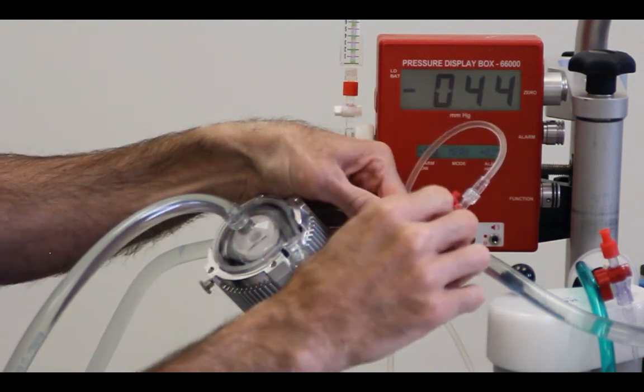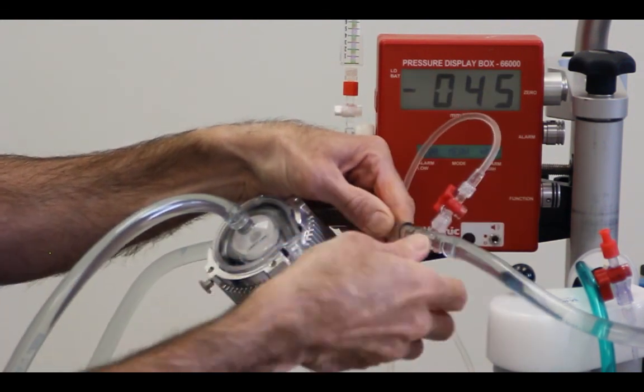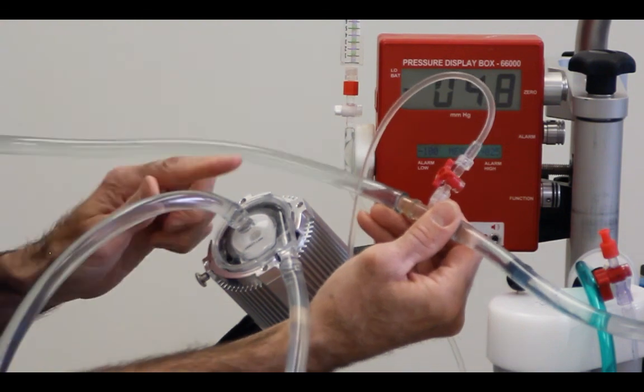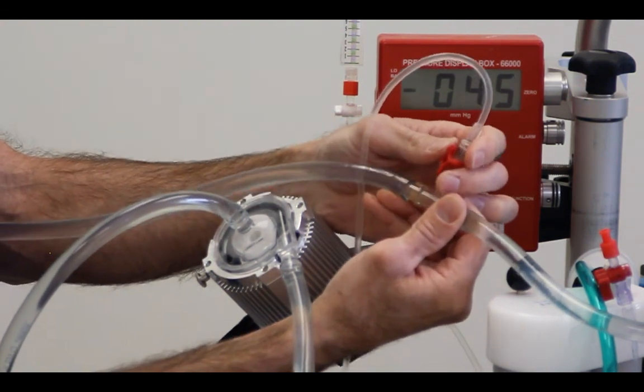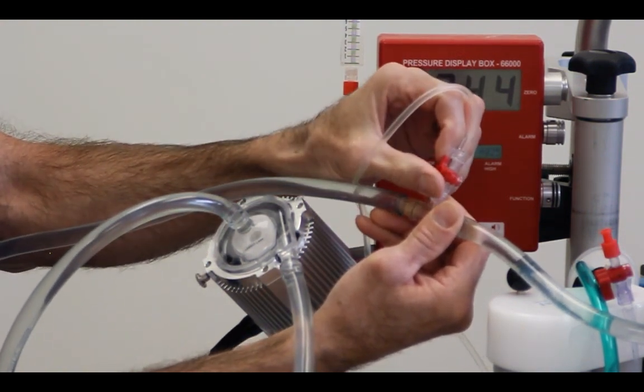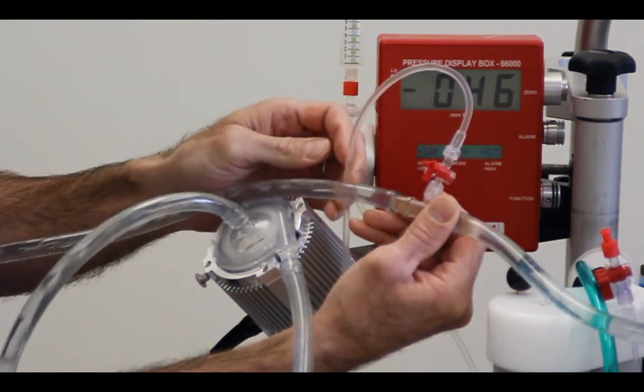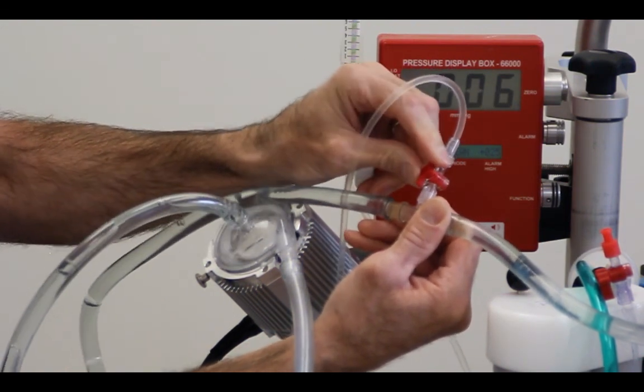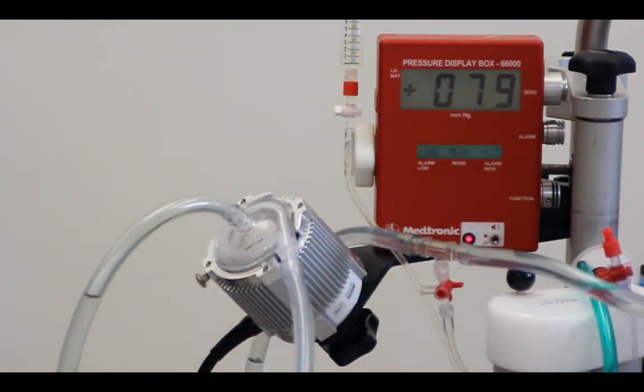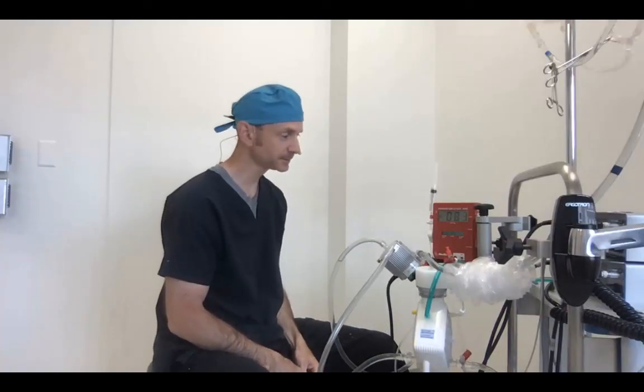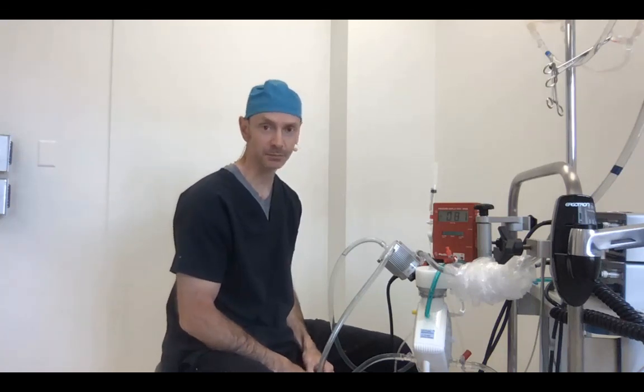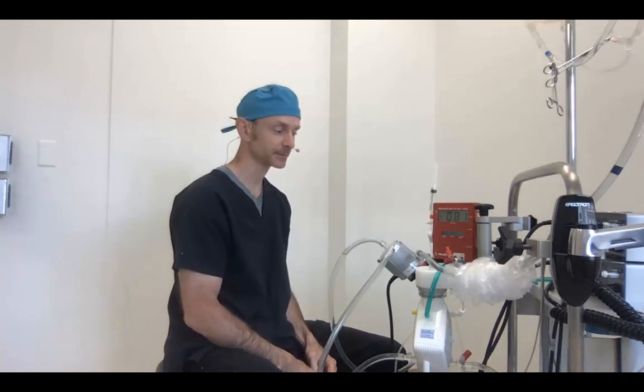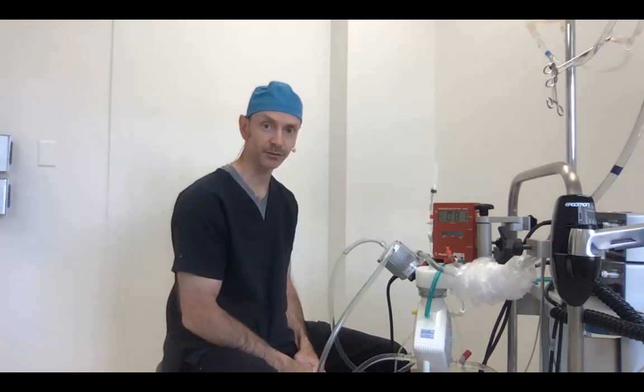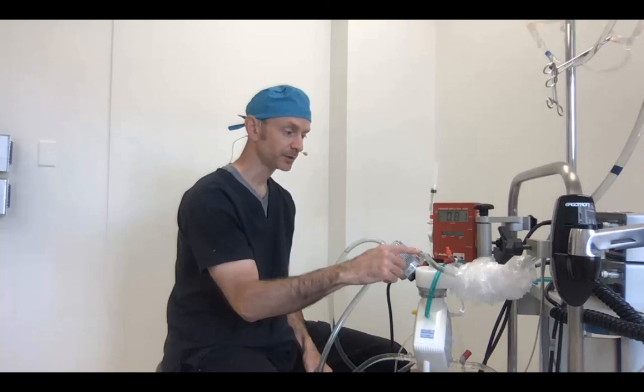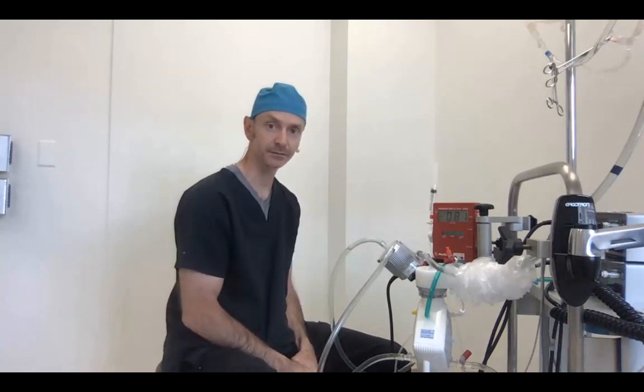So here we are, minus 40. And I'm going to turn this to open in, keep an eye on the pump here. The line is opening in 3, 2, 1, now. And I'm turning it off. That was pretty instantaneous. Maybe we go back and watch it in slow time, but it was less than 2 seconds. And that is why we generally don't include openings on the venous line for an ECMO circuit.